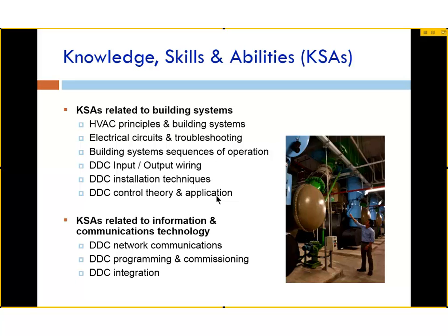I heard somebody mention Wonderware and Allen Bradley. Those are primarily found in the industrial marketplace, while in the commercial HVAC marketplace, you run into the Johnson Controls, the Siemens, the Delta Controls, etc. And at that level, at the programming level, none of the systems communicate. They may have similar objects or standardized objects within their programming schema, but each one programs their controllers in their own software. So it's a disservice to the students to focus on one system over another.